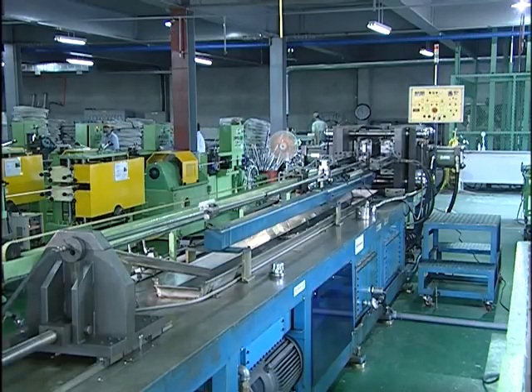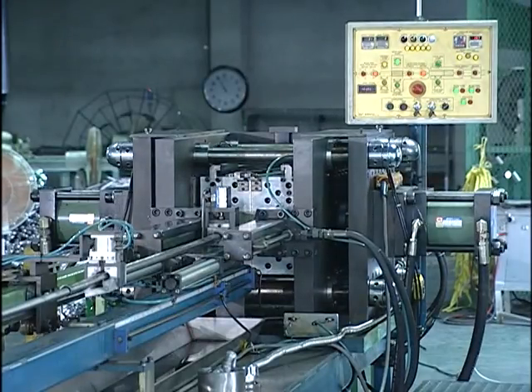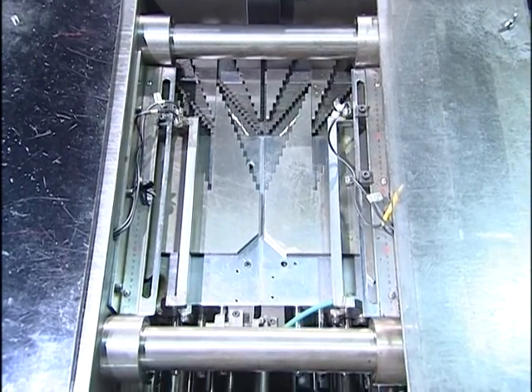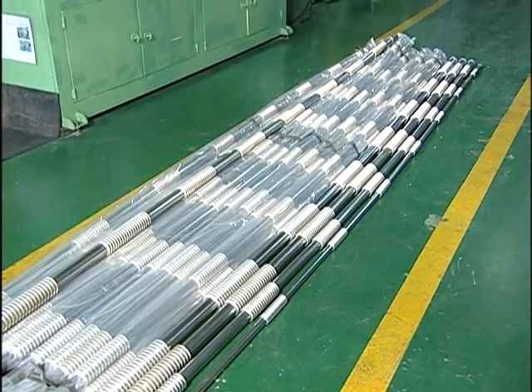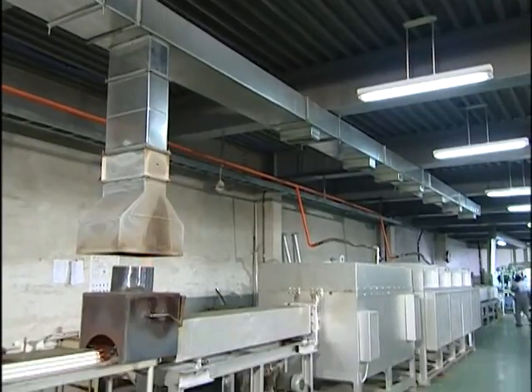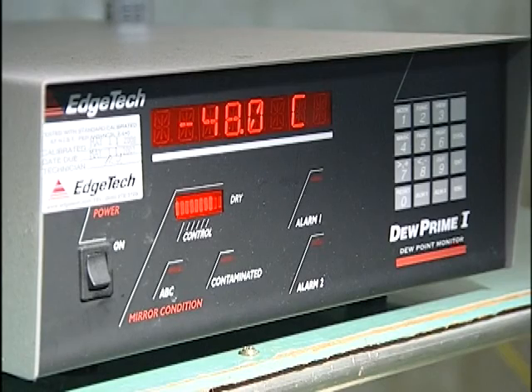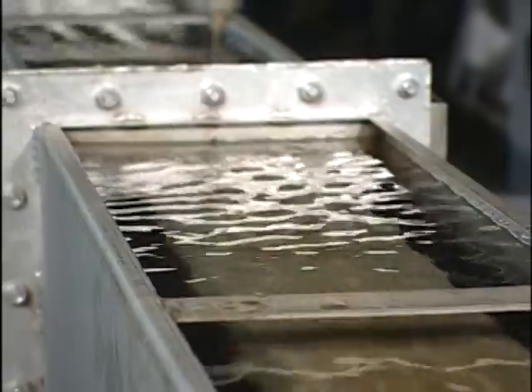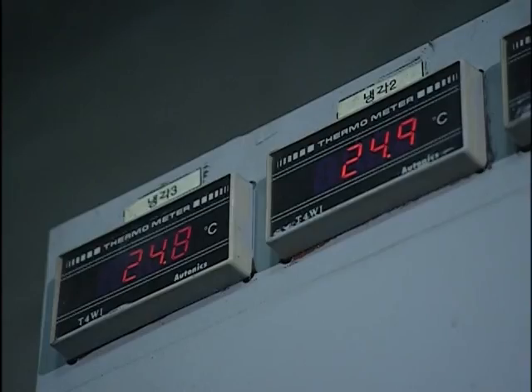Second, the new technology of buckling forming is applied to increase the life of stainless steel corrugated tubes, and the tubes are formed under optimum temperature conditions. Therefore, the thickness on each part of the groove remains the same. Third, cooling is done after heat treatment by using a freezer, automatically controlling the dew point and the temperature of the coolant. This keeps the temperature of cooling constant regardless of external conditions, making the result of the heat treatment consistent.